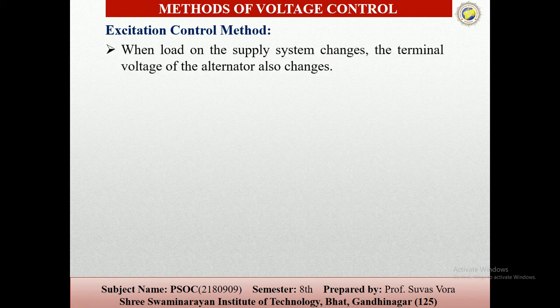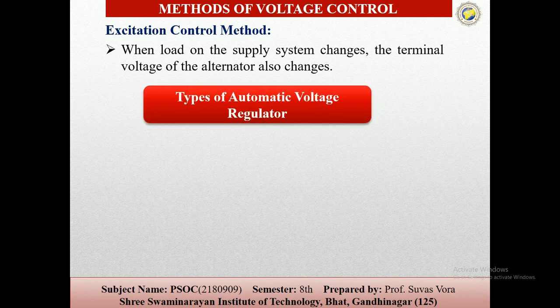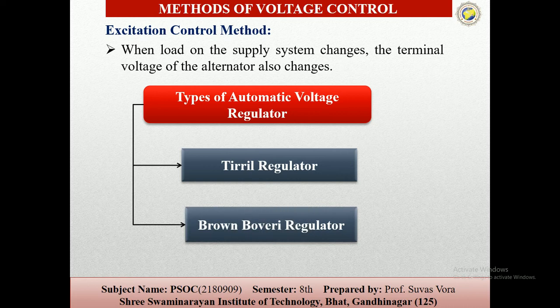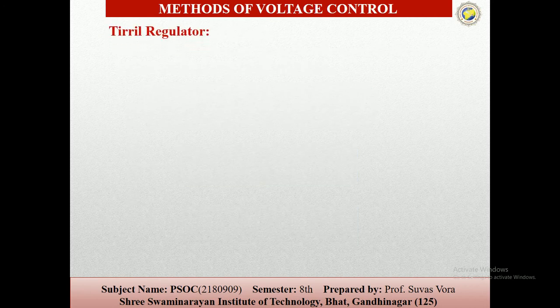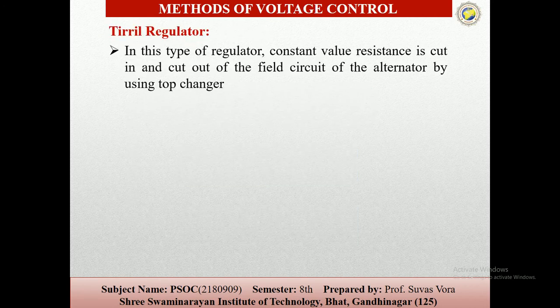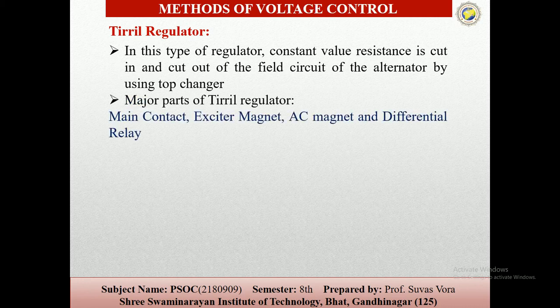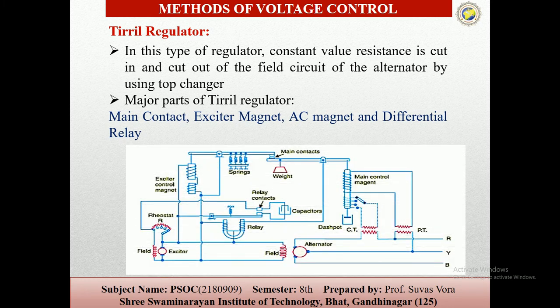When the load on the supply system changes, the terminal voltage of the alternator changes. So there are two main types: the Tirril regulators and the Brown-Boveri regulators. The Tirril regulator is nothing but a constant value resistance being cut in and out of the field circuit of the alternator by using the tap changers. So these are the major parts of the regulators; you can see here the method of the voltage control system.